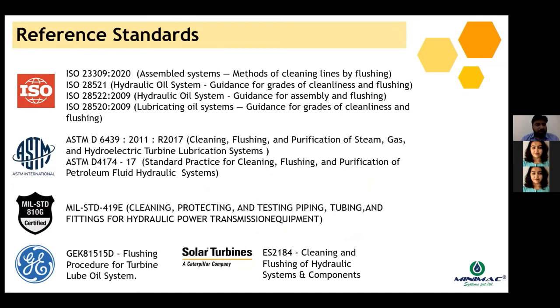We have compiled certain international standards and documents which are very important for oil flushing activity. These are certain ISO standards for flushing and cleaning of pipelines, for hydraulic systems and for lubrication systems. Then we have ASTM standards, which are used for various hydraulic and lubrication systems as well. The third one is MIL standard, normally used for the hydraulic power transmission equipment.